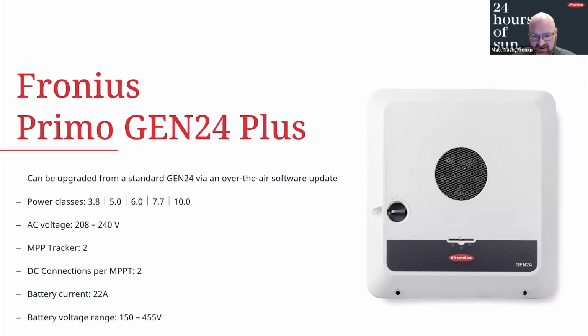This can be upgraded from a standard Gen24 via an over-the-air software update through our SolarWeb monitoring portal. It's the only one that is in the market that can do so. Our power classes range from 3.8 to 10 kilowatts with plenty of power classes in between. It is a single phase inverter, so 208, 240, has 2 maximum power point trackers with 2 connections per power point tracker. It has a current rating for the battery at 22 amps, and the battery voltage range is in between 150 and 455 volts.